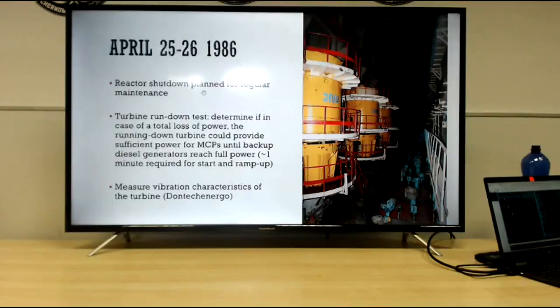There were two main tasks. One was to determine what would happen in case of a total loss of power to the plant — if the running-down turbine, still producing electricity due to its inertia, could hold enough inertia to supply power for about a minute, until the backup diesel generators started and could power up the circulation pumps to circulate water through the reactor. The other task was to measure the vibration characteristics of the turbine.